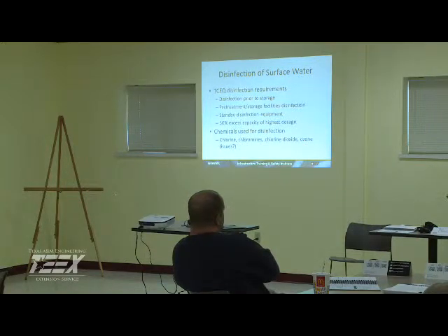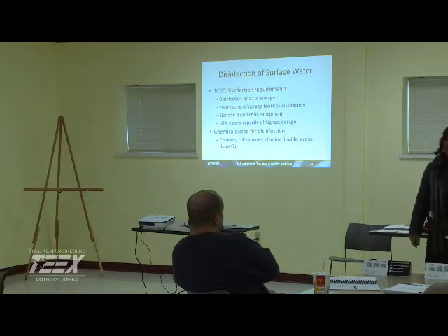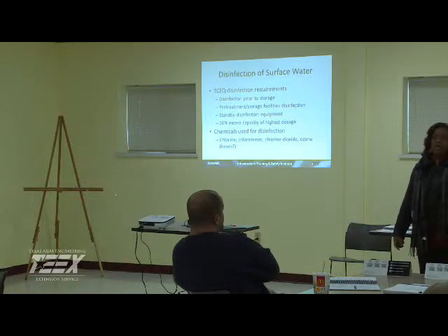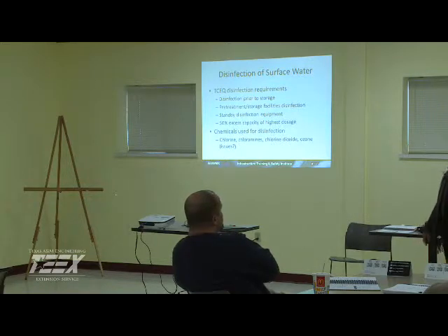Ozone also creates issues because, again, it's very unstable. It's oxygen, O3, very unstable. The other drawback is there's no residual. It doesn't last long, so it's difficult to check the effectiveness of it, although it's probably much more potent than chlorine. It will kill the Giardia and Cryptosporidium. It kills everything. It has a very high initial strength, but it's not good for maintaining the system. That's the reason it's very difficult to do a residual.